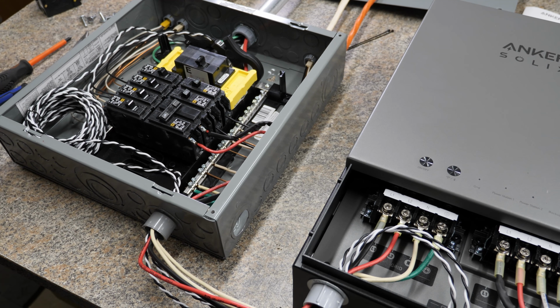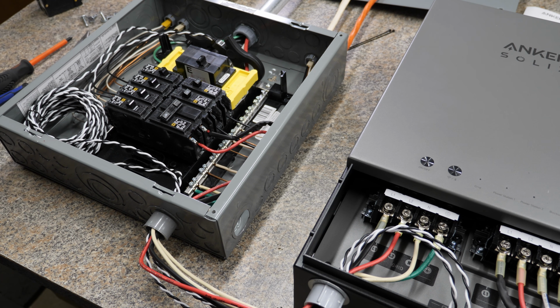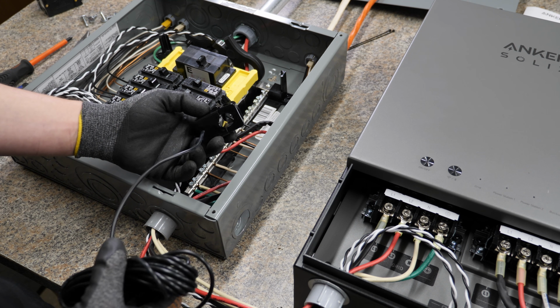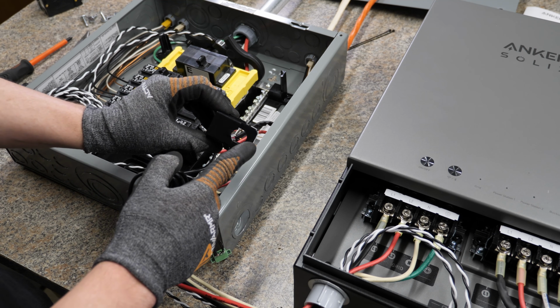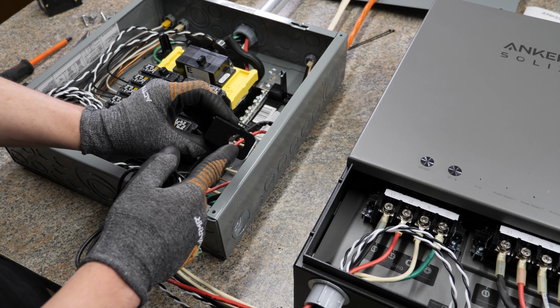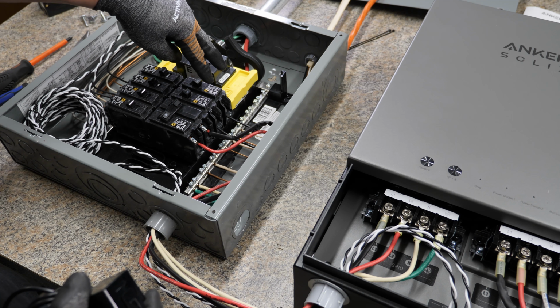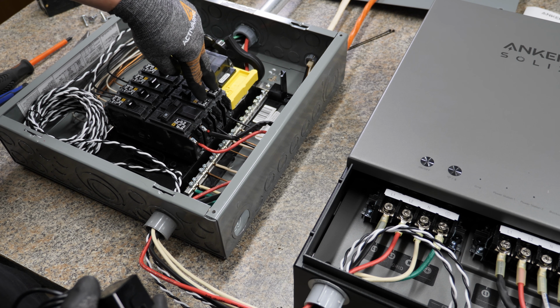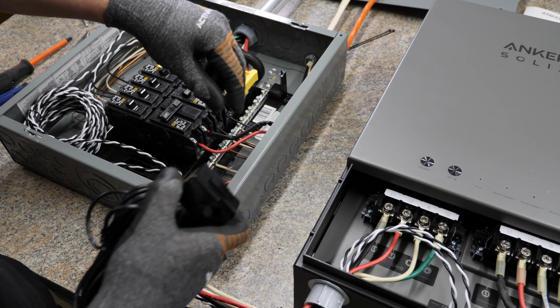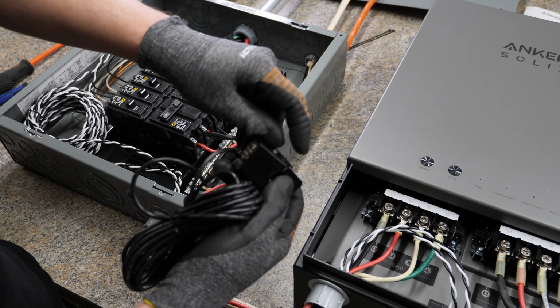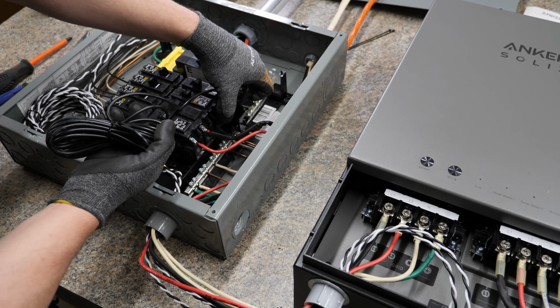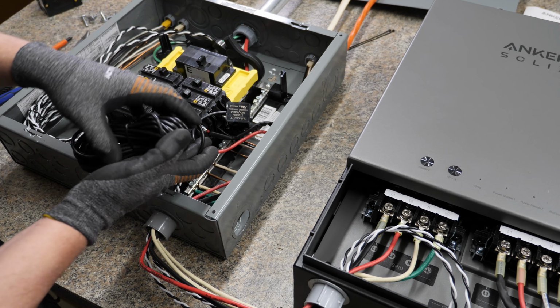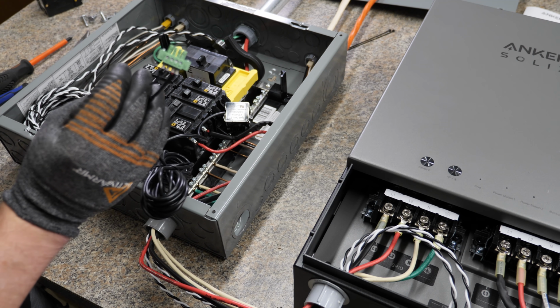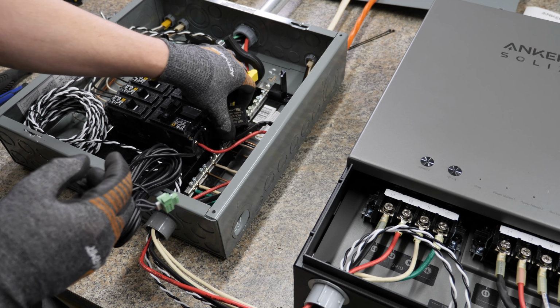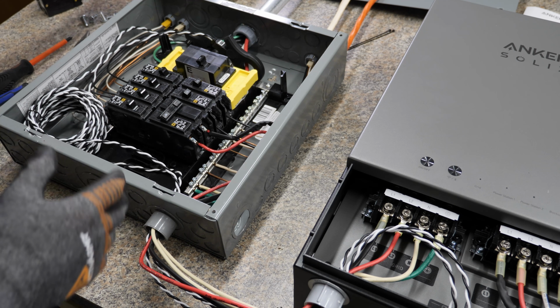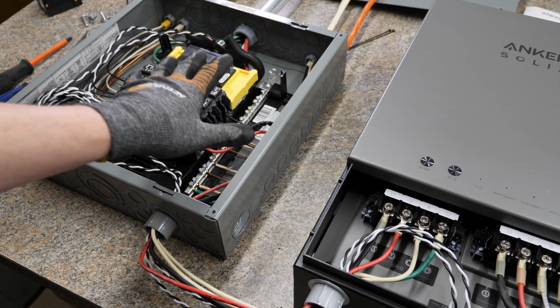I did want to mention, again, if you have an existing AC coupled solar system, you would wrap this CT clamp around one of those wires. For example, if your AC system was coming in through these circuit breakers right here, you would just clamp to one of the wires. That's basically it, and the other side goes in the home power panel. But we can't do that right here for our simulation.